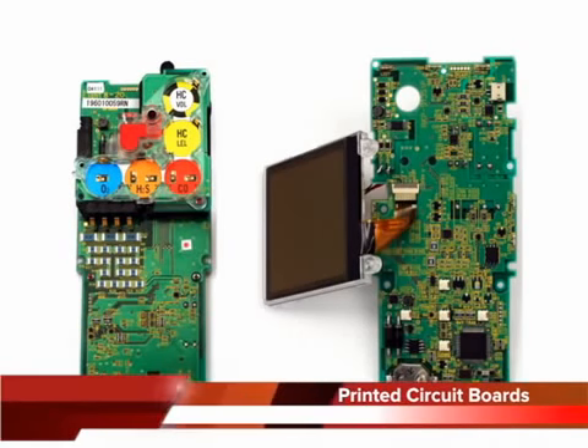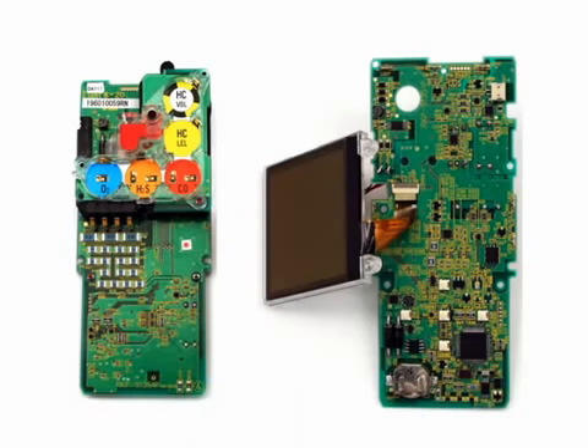The primary function of the GX 2012's printed circuit boards is to amplify the signal sent to them from the gas sensors, convert the signal to a measurement of gas concentration, display the gas concentration on the LCD, store peak, STEL, and TWA readings, and activate the alarm circuit if an alarm point has been reached. The circuit board also monitors battery level, battery failure, and sensor failure. They also control the GX 2012's time function and various operating modes.